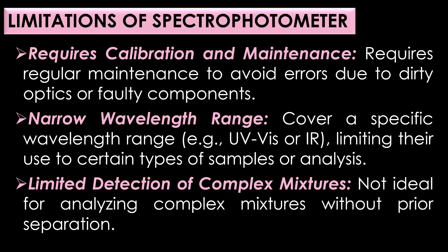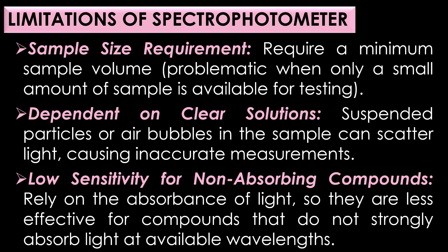The fifth limitation is limited detection of complex mixtures — spectrophotometer is not ideal for analyzing complex mixtures without prior separation, as the instrument can't distinguish between different substances that absorb at similar wavelengths. The sixth limitation is sample size requirement — some spectrophotometers require a minimum sample volume, which can be problematic when only a small amount of sample is available for testing.